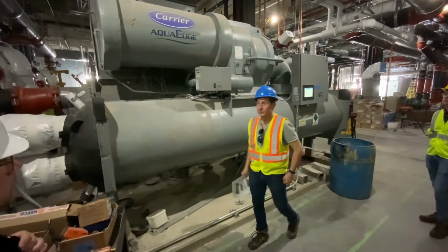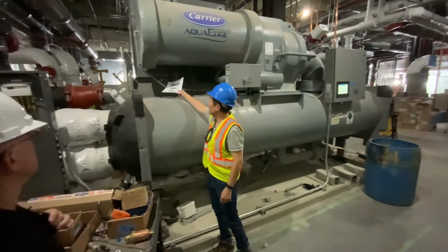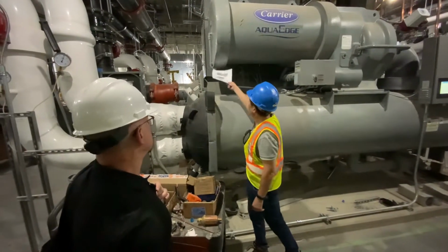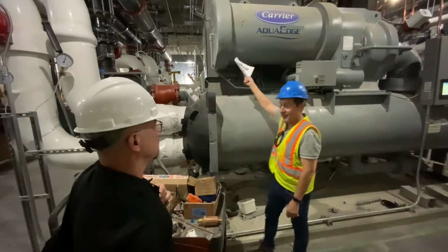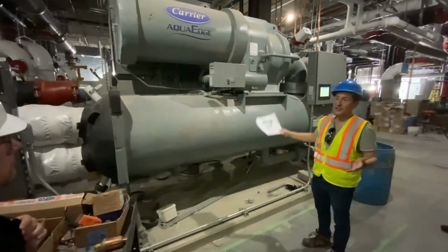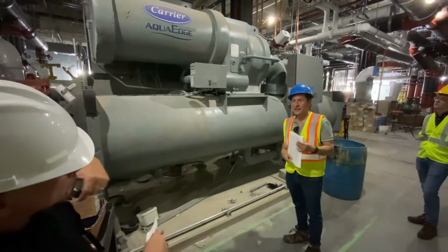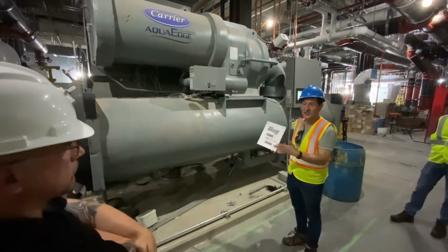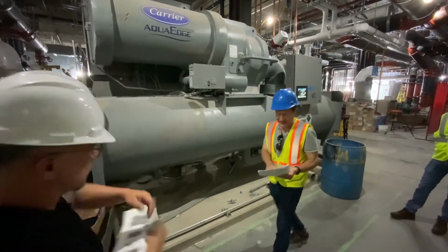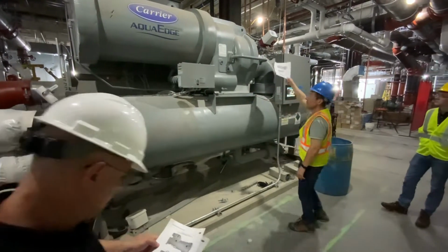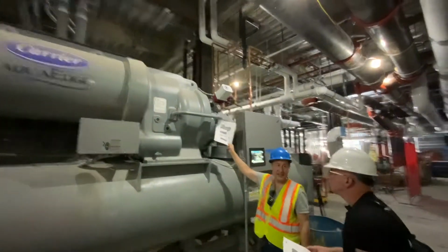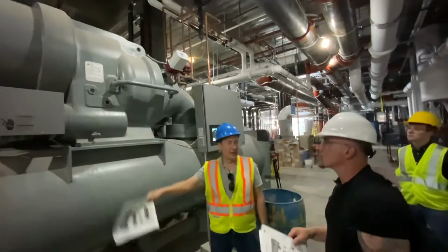It's a refrigerant cooled motor, so you're getting liquid from the condenser here, it comes through an expansion device back here, and provides the cooling liquid that cools the motor. Okay? This is a two-stage compressor, not like a typical compressor you see, one stage. It's actually two stages of compression, two wheels. On the first wheel, your inlet guide vanes, which is your actuator right here. There's suction coming up through the inlet guide vanes, controlling the gas flow to the compressor.